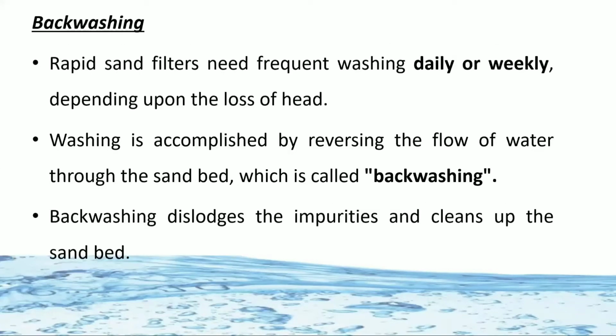So how does backwashing take place? The rapid sand filter needs frequent washing. It may be daily or weekly. In the slow sand filter, we have seen the cleaning required weekly or after some months. So in the rapid sand filter, the cleaning is required daily or sometimes weekly. This washing is accomplished by reversing the flow of water. Means here we have to reverse the flow of water through the sand bed, which is called backwashing. The word itself suggests back, means reverse washing.